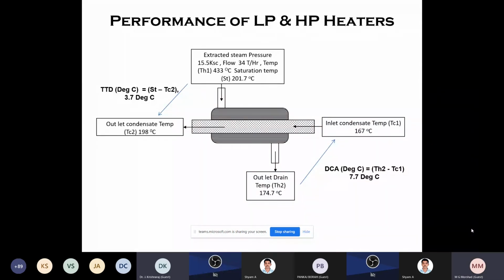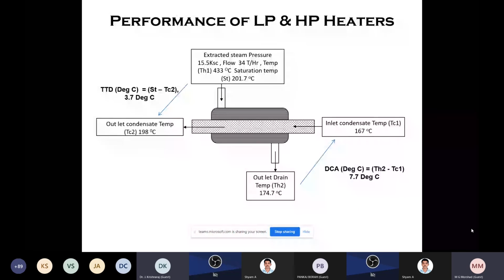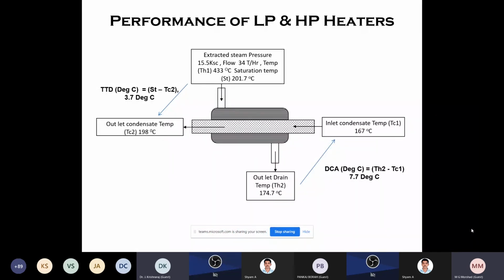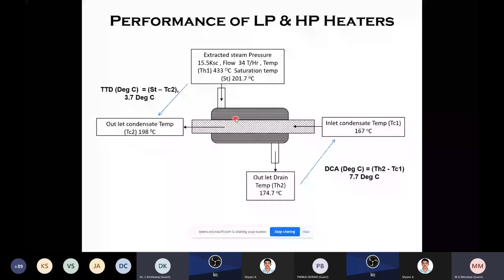Now, LP and HP heaters, because the water coming to the boiler feed pump or to the boiler comes through the HP and LP heaters. It is called the preheating stage. So after the condenser, the water comes back to normal temperature, then preheating takes place, and only after that does it go to the boiler feed pump and the feed water. When preheating is taking place, normally steam is extracted from the turbine and put into the heater. So water flow will be like this. Steam will go here and come out. So steam energy will be condensed here and the drain will come out, and the heat exchange will take place.